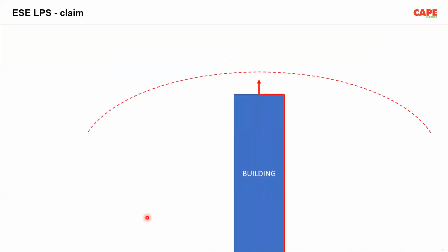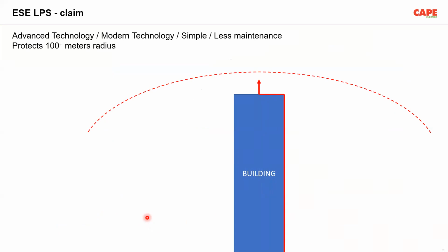Now, typically it looks like this. You have a building. There is one rod which the manufacturer says is protecting not only your building, it protects all your neighbors and probably the whole village as well. And they call this modern technology, advanced technology, and very, very attractive names. The claim is that one rod protects hundreds of meters. It has a counter, so whenever there is a lightning strike, your counter will count 1, 2, 3, 4, 5, 6, like that.